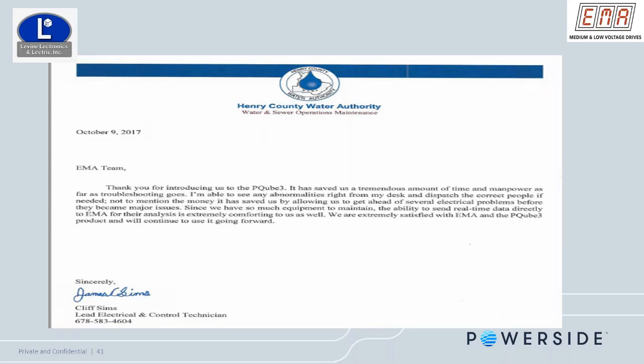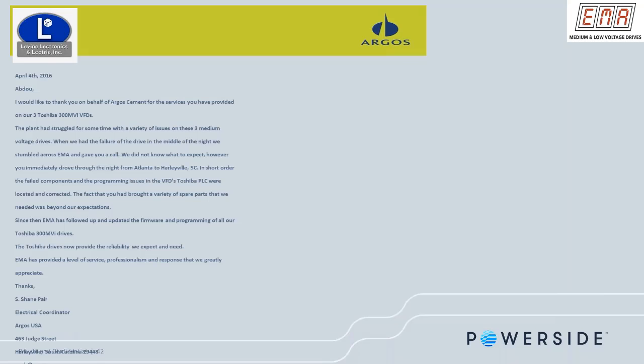Over the years, our customers have given us some feedback. This is actually from Henry County Water, where they have these drive scans. One of the feedbacks we got from Henry County is that they love the product, and in terms of troubleshooting, they don't even have to put on their arc flash suits anymore, because they can actually troubleshoot the drive from the convenience of their computer. They don't have to go to the drive - they just log onto the computer and can see what is happening on the drives. So they are very impressed and bought a significant amount of drive scans and put them on all their large VFDs.